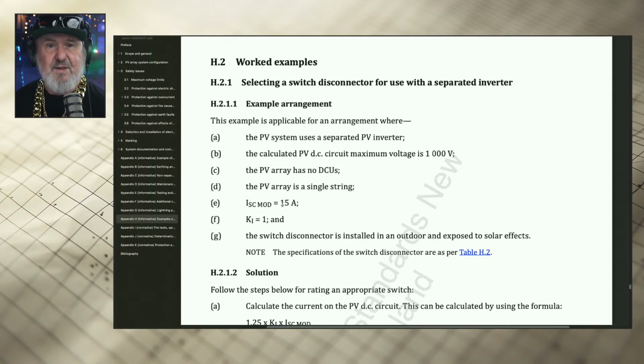The short circuit rating of the module is 15 amps, known as ISC mod, and that'll be written on the data sheet. It'll actually be mandatory on the back of the panel on the compliance label. And the K factor, the bifaciality factor. Now, I did cover this last week, so if you're wondering what on earth is K, it's not Special K, it's just K, I, and it's the amount of extra input from the back surface of a panel. Now, bifacial panels generate current on both the front and the back, whereas a conventional, and I call it conventional because it used to be the most common type, monofacial panel only generates current from the front face. So in this case, we're just using monofacial, and therefore bifaciality is 1, meaning there is none. So we don't have to increase our current rating from our modules to allow for bifacialness.